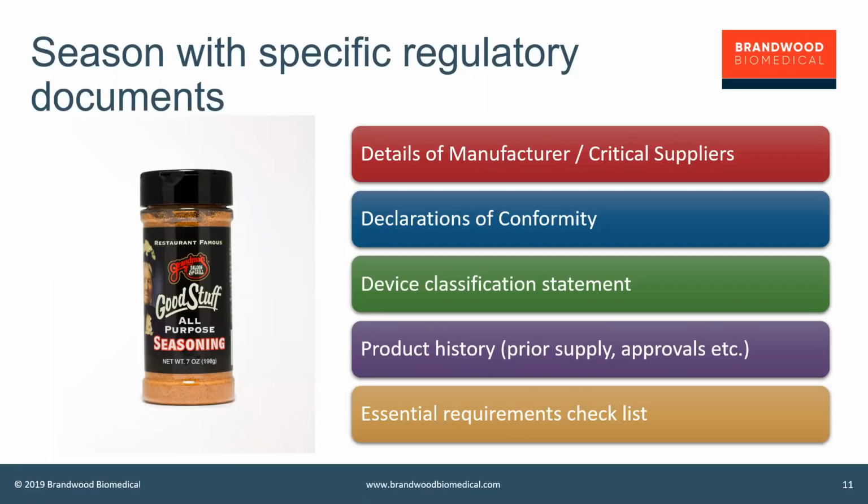If you have years and years of experience of your previous device on the market and you've not had any major issues with it, you should be using that to support your safety and effectiveness claims for your new device. No, it's not the whole thing, but it's really going to paint a picture for the regulator that suggests you as a company know what you're doing, you can do it well, you have the controls in place, and that your previous history demonstrates that.